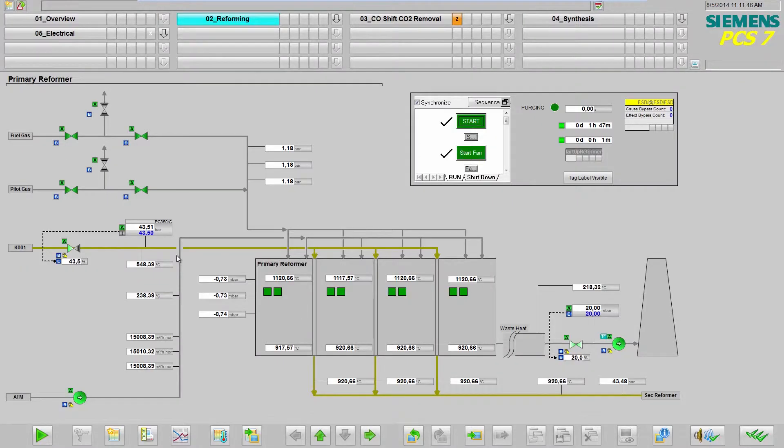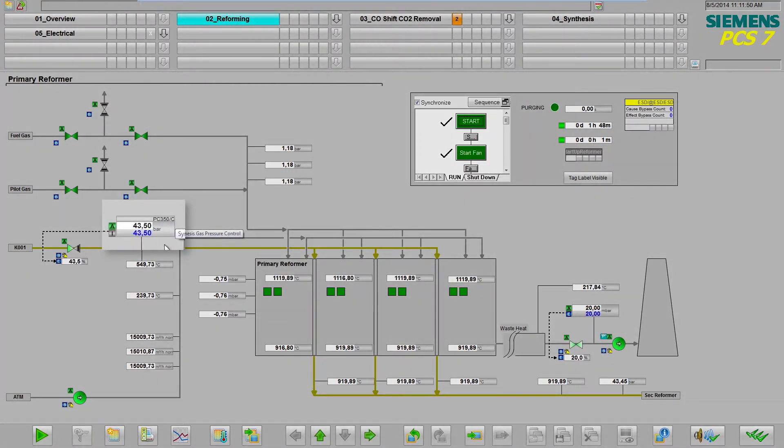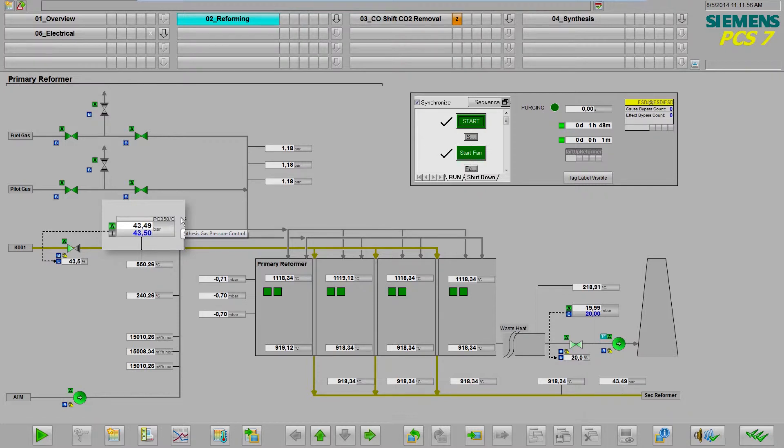Let's take a look at the synthesis gas pressure measurement. The optimal operating range is narrow, between 40 and 43 bar. An alarm is triggered at 44 bar.